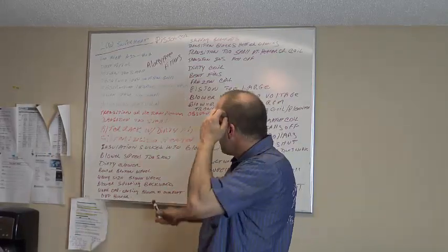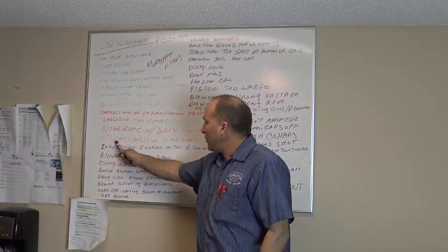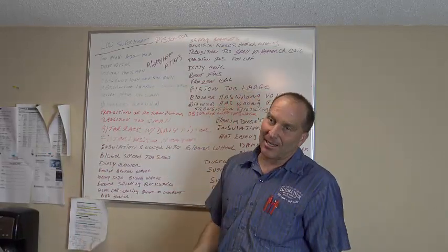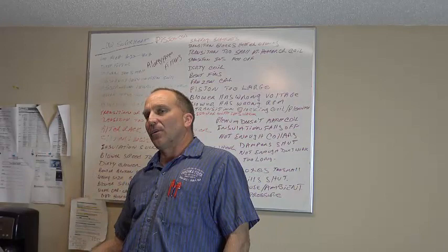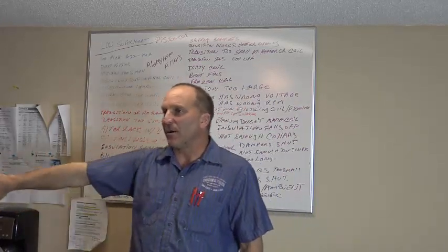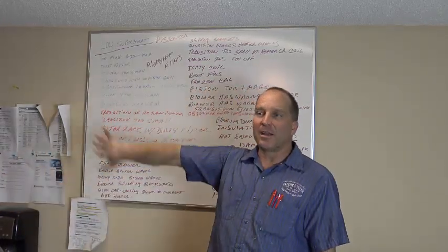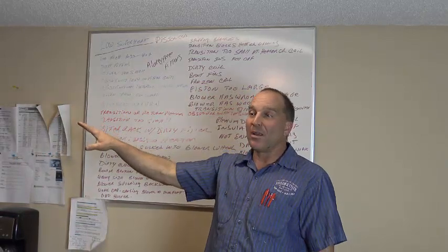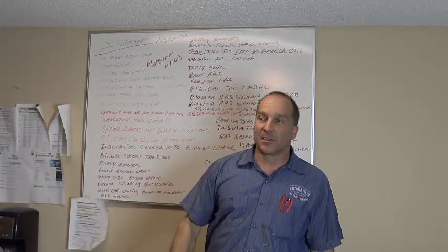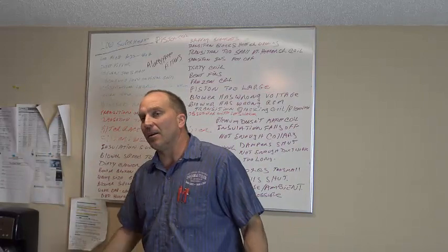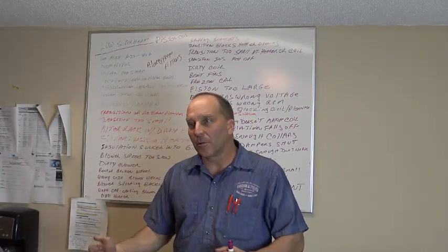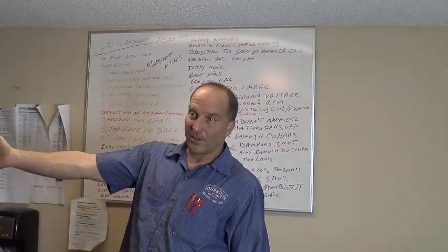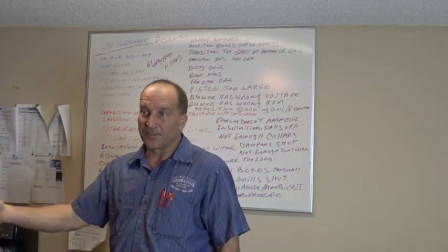Okay? So also, if you have a filter inside your heater, a lot of times you put a heater in, there's a filter that comes with the system, you leave that filter in there, nobody ever knows it's in there. It's in there for 20 years. You're servicing the air conditioning, you're servicing the heater, and nobody opens the blower compartment and looks to see there's a filter in there that's blocking the airflow through.